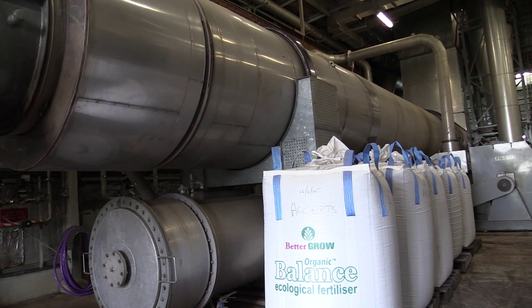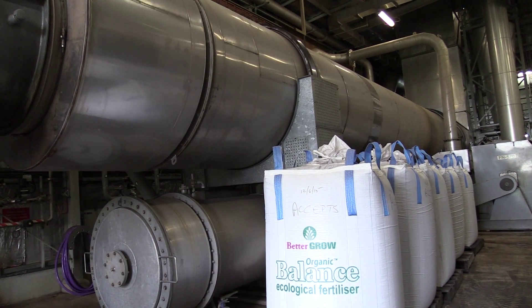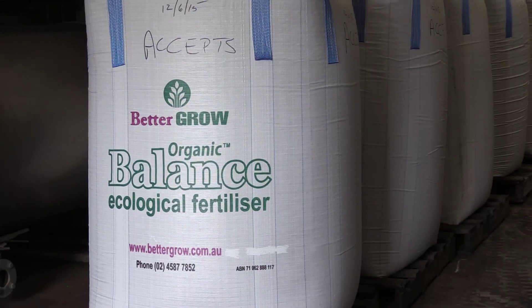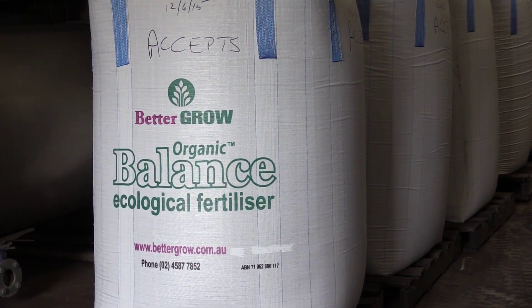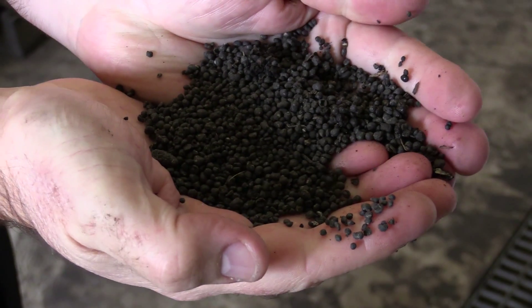The digested food waste we send to a dewatering process. We separate out the water fraction. We treat it on site to a level that's acceptable to Sydney Water to discharge into their sewer system. The digested food solids we take through to a drying process. We use the waste heat from the generators — the exhaust heat, which is running at 430 degrees Celsius — as a heat source to dry the sludge and make fertiliser.